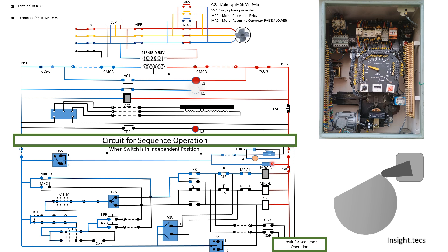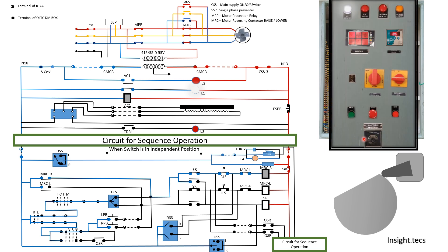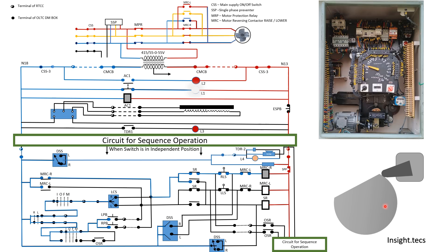The first contact that closes sends power toward the hooter circuit — the hooter is placed on the RTCC panel on the outside and continuously indicates that the process of raising the tap position is in progress. The second contact getting closed energizes the SR contactor. Once SR is energized, its NC contact becomes NO, meaning it should open. However, a third DSS contact closes simultaneously, sending power forward toward MRCL.